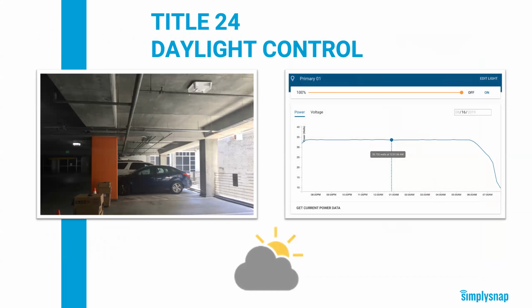Now, in energy codes like Title 24, there are criteria for how to control the lights depending on whether it's full sun, nighttime, or partial sun. At night, the lights have to be on. In a full sun scenario, the lights have to be off. And in those times in between, like sunrise, sunset, or on cloudy days, lights need to be continuously dimming such that you're maximizing energy savings while preventing light levels from dropping below the designed illuminance, which is a big deal for garages for safety purposes. In our experience, and from what we've heard from customers, you just can't do this with a system that has an integrated daylight sensor in every light. You need a daylight sensor pointing out towards the natural light that is controlling all the lights.